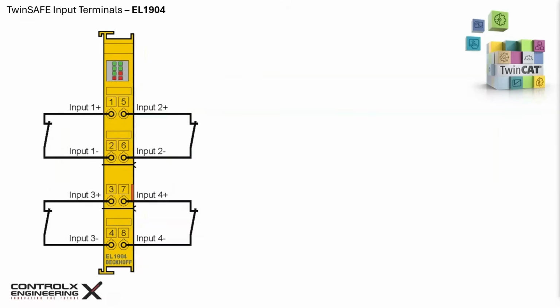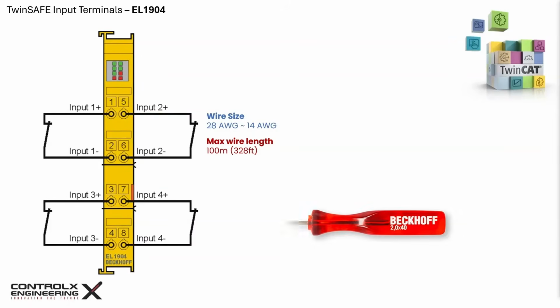The inputs 1 to 4 can be connected to either normally closed or normally open contacts. We can make the appropriate logic decision when we program the safety in the next tutorial. The connection points accept wire size from 28 gauge to 14 gauge. I highly recommend using wires terminated with ferrules, which can easily be inserted into the terminal point. Also keep in mind that the wire length should not exceed 100 meters or 328 feet. These connection points are spring actuated and require an insertion tool like this one from Beckhoff. You can also use any flat 2x40mm screwdriver.